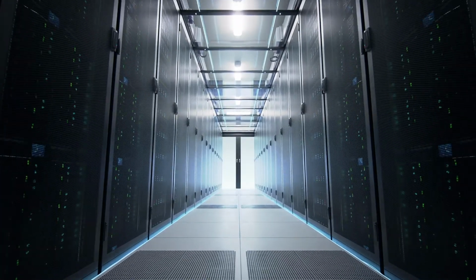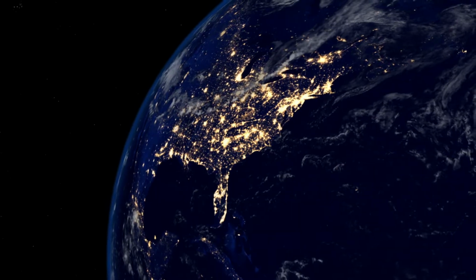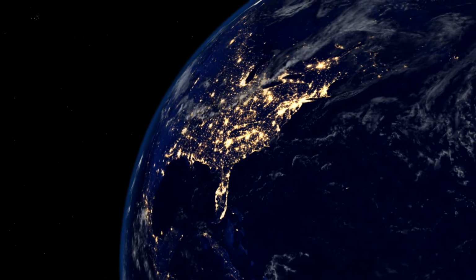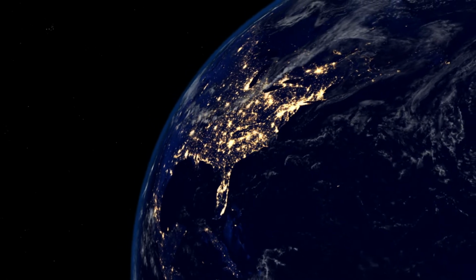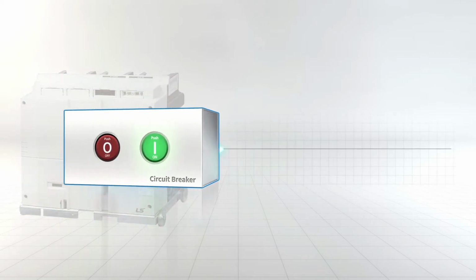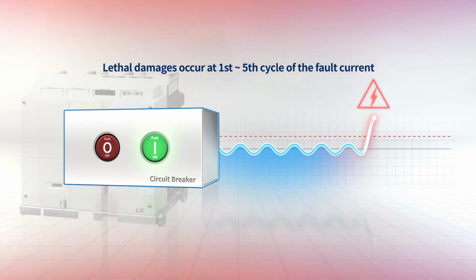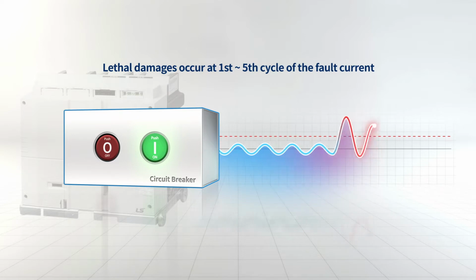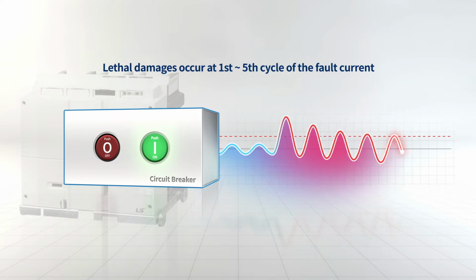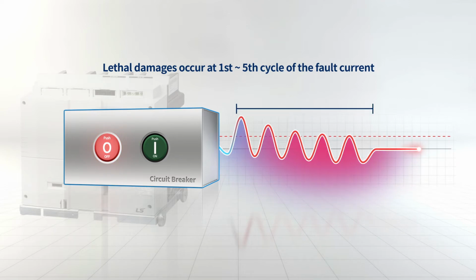Accordingly, reducing fault current rapidly to protect electrical power systems is paramount. A solution optimized to these roles is Superconducting Fault Current Limiter. So far, to prevent damage due to fault current, we used to mostly depend on a circuit breaker. However, it is limited in preventing the initial fault current from damaging the system seriously only with a circuit breaker. From diagnosing the fault of the relay to operate a circuit breaker, it takes at least 5 cycles. But at that time, the biggest fault current is flowing.